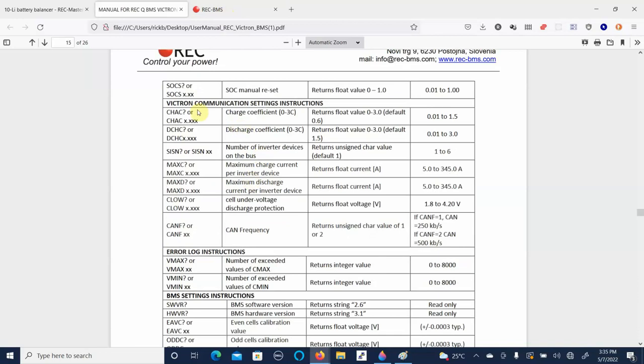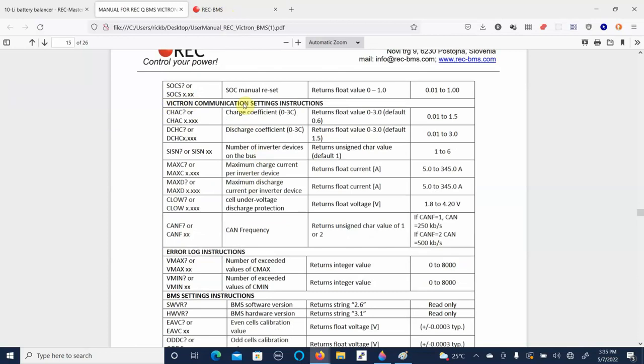There are some other charge coefficients here for Victron communications, which we'll get into later. But for a starting point, you just leave everything exactly where they are. And then you can do some fine-tuning later. So the idea is using the default parameters, you can get the system up and working, maybe change your CAN frequency if you have to, set your shunt variable, and set the system capacity. And you're good to go.